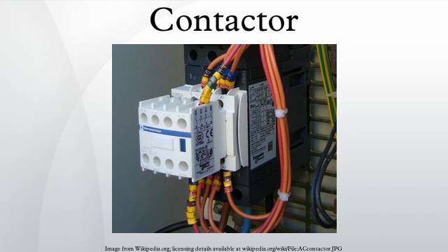A contactor is controlled by a circuit which is a much lower power level than the switched circuit. Contactors come in many forms with varying capacities and features. Unlike a circuit breaker, a contactor is not intended to interrupt a short circuit current. Contactors range from those having a breaking current of several amperes to thousands of amperes and 24 VDC to many kilovolts. A physical size of contactors ranges from a device small enough to pick up with one hand, to large devices approximately a meter on a side.